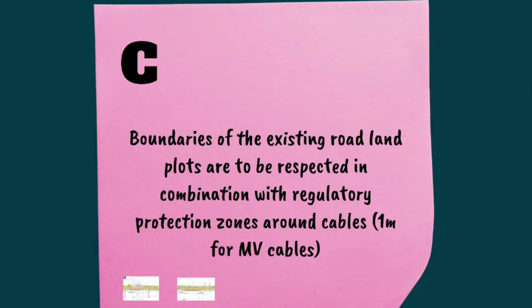But also pay attention to the protection zone around the cable itself, which according to current legislation extends at least 1 meter in either direction around the cables. This should not extend onto adjacent land plots, and ideally you should try to fit everything within the same land plot, including the protection area around the cables.